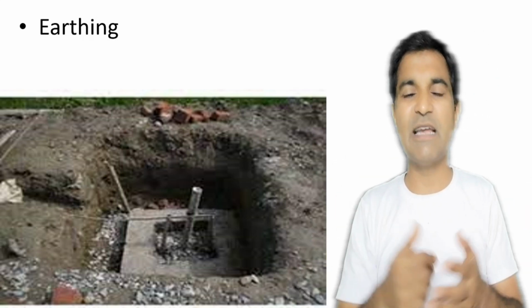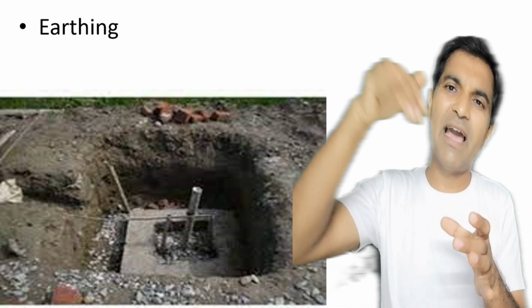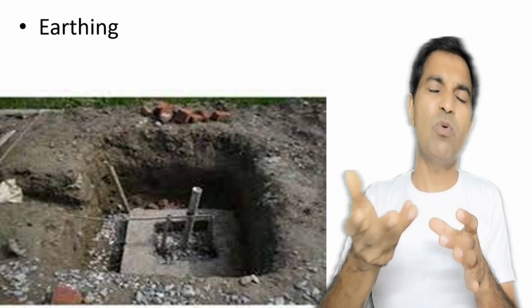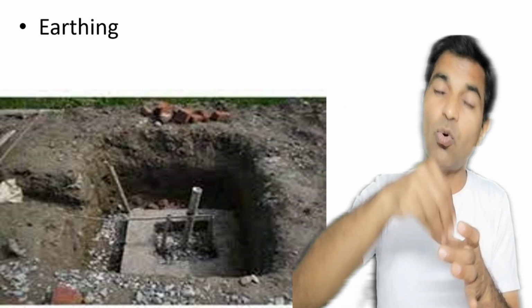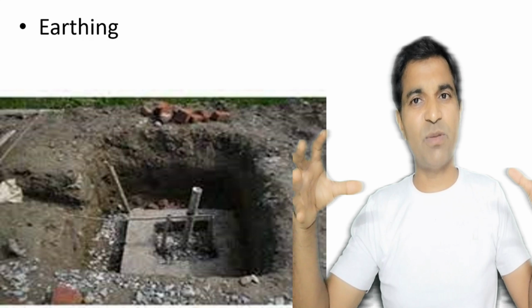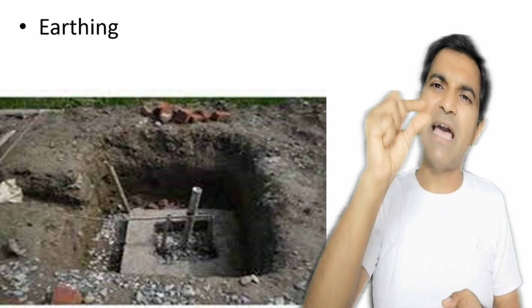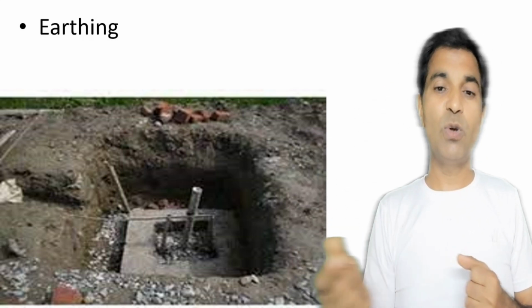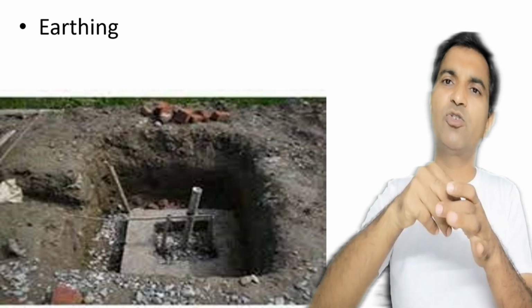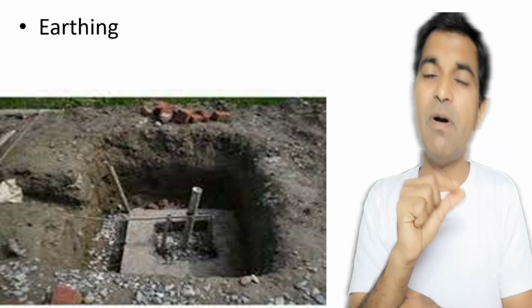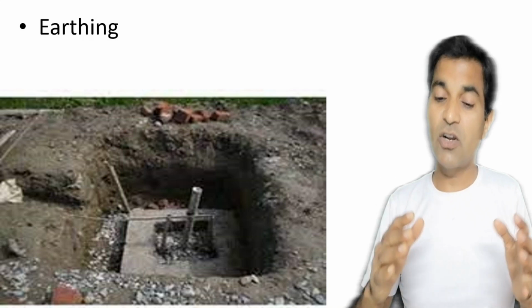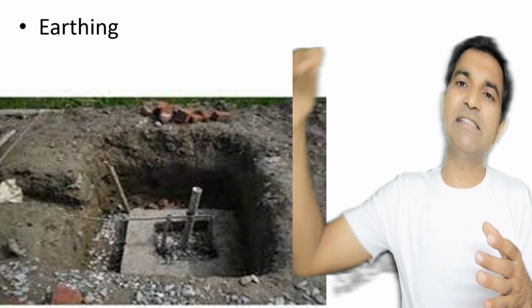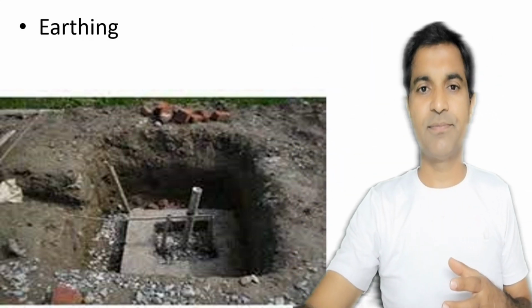You might have seen this type of earth pit. An earth pit generally has coal, mostly charcoal, and salt, so that it can retain moisture for the maximum time and have minimum resistance. Salt is added so that the resistance is minimum, and hence the short circuit current can easily be grounded.